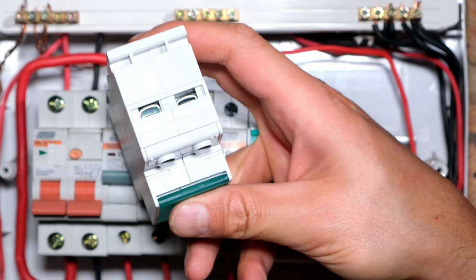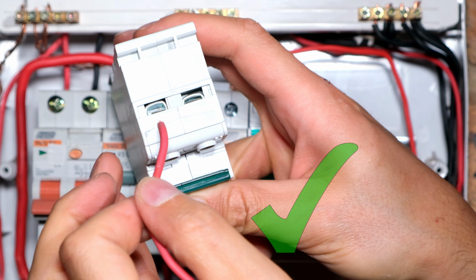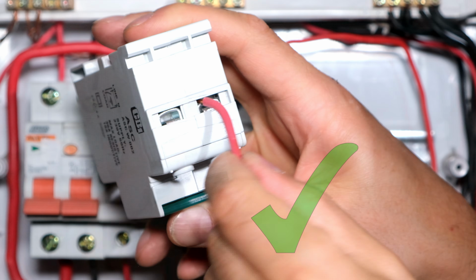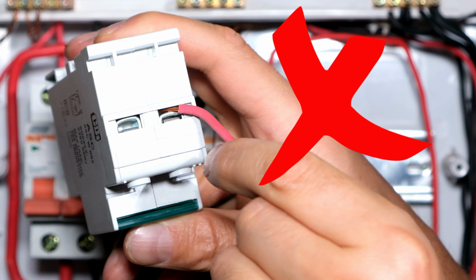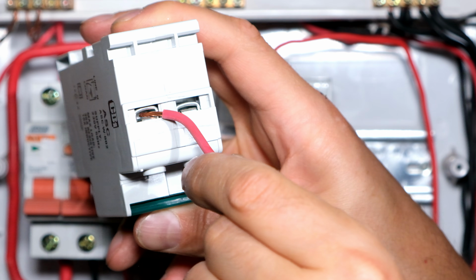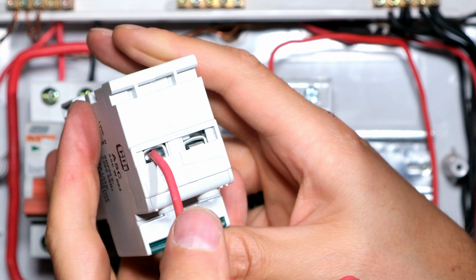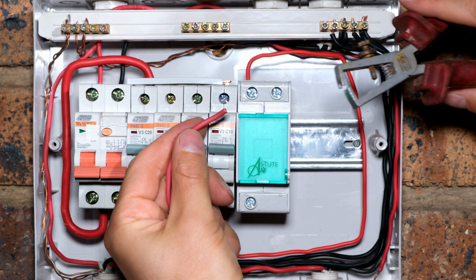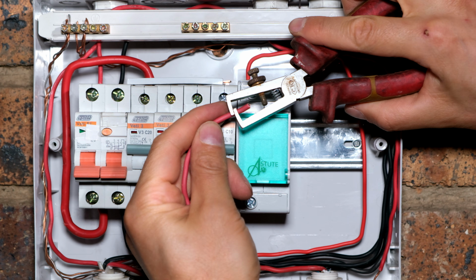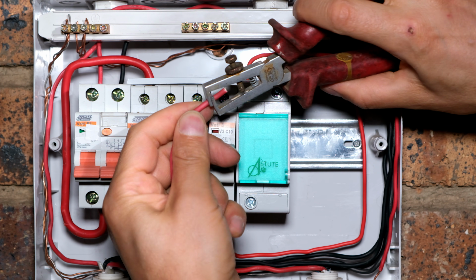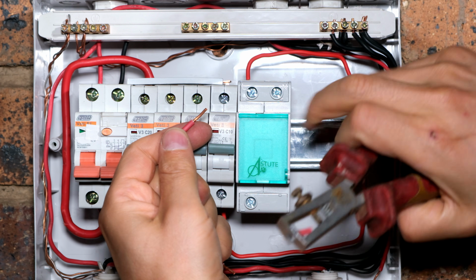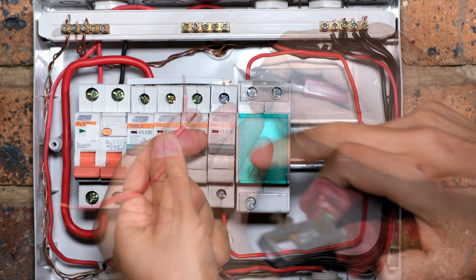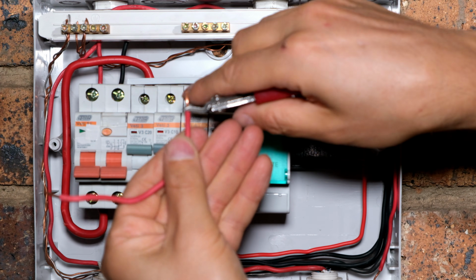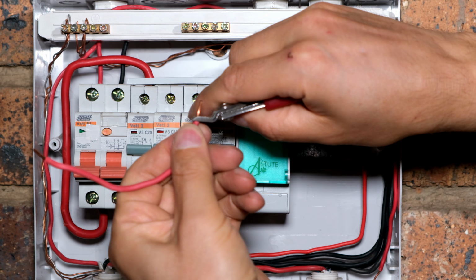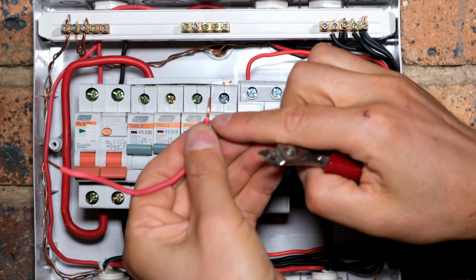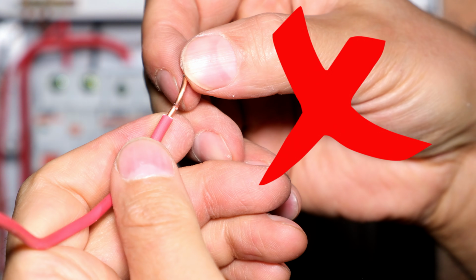Make sure that when you insert the wire into the circuit breaker or the timer, it goes in there. It must not be on the top. There I'm on top of the clamp. That is incorrect. I must be underneath where the clamp can now squeeze the wire. Now the amount of wire to remove is only about 1 centimeter, 10 millimeters. Preferably use wire strippers because they do not nick the copper. Please be very careful if you are using side cutters to strip your cables, because what often happens is the copper gets nicked. So for example, this is wrong.